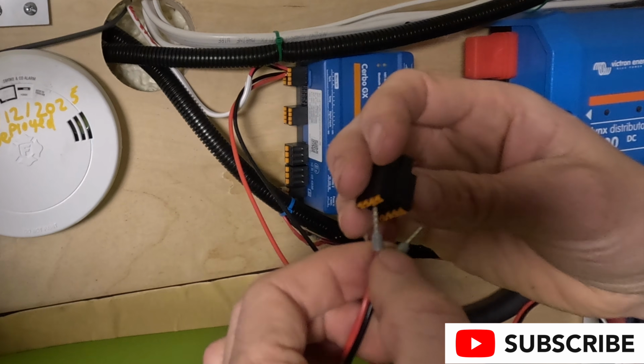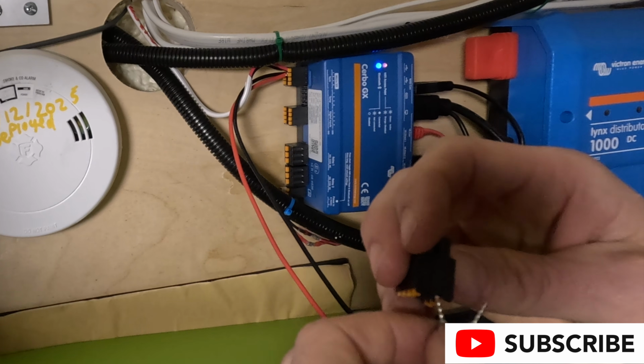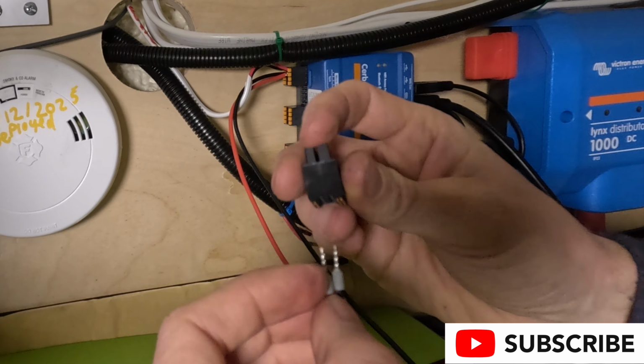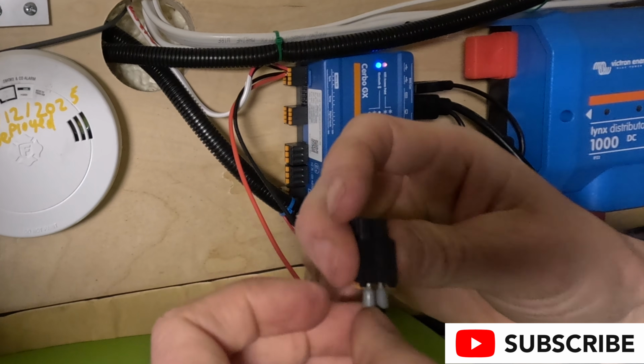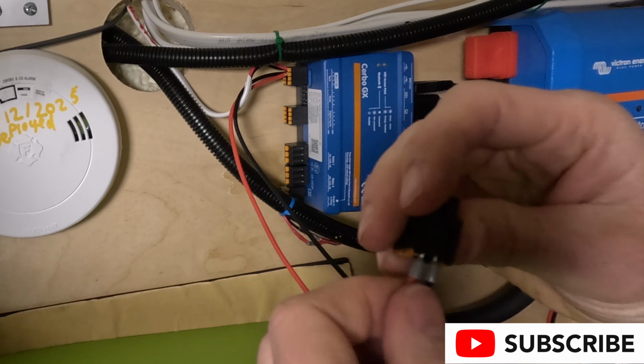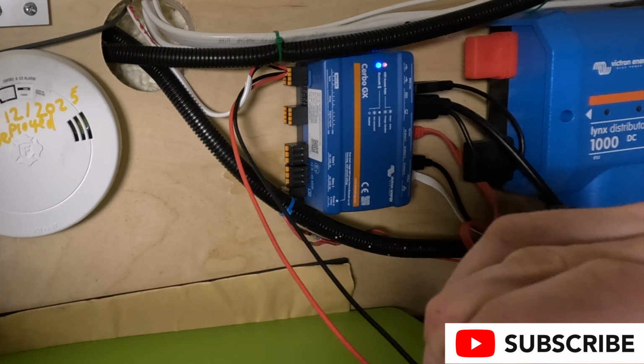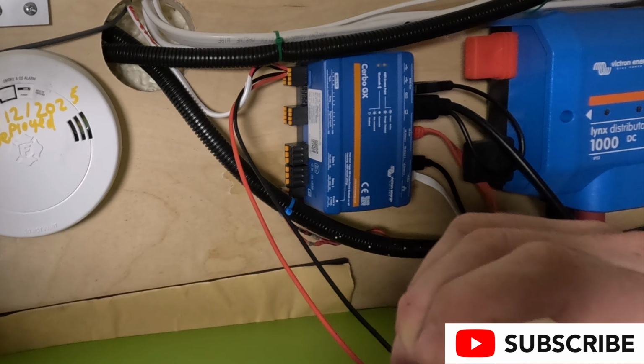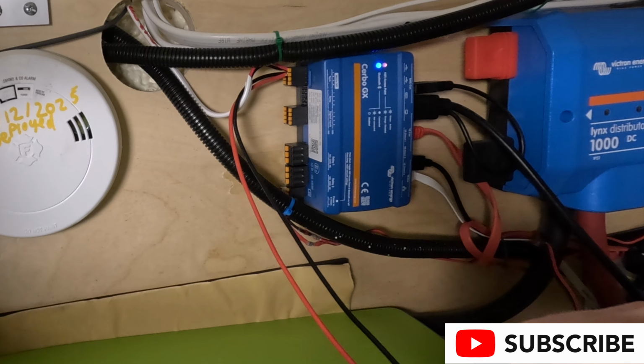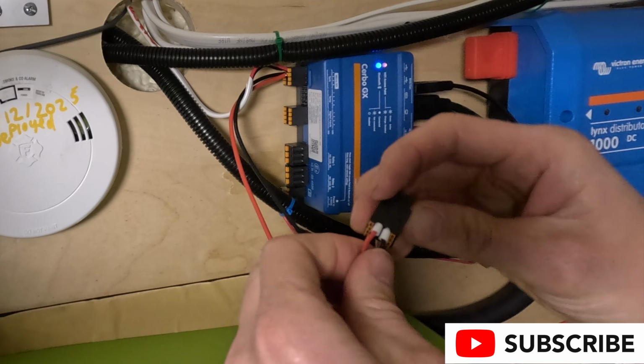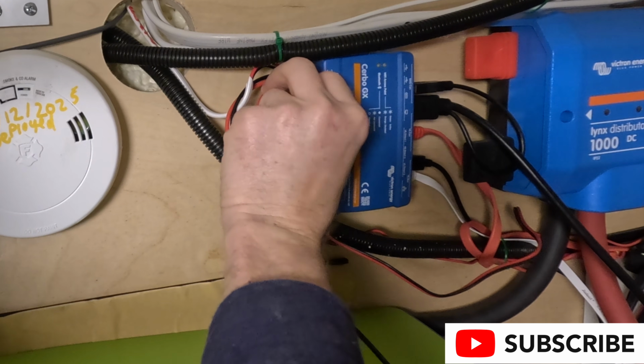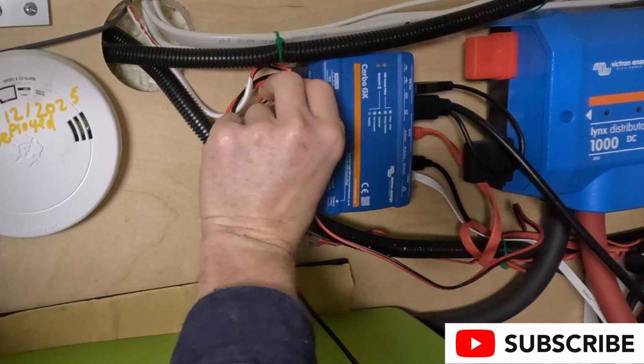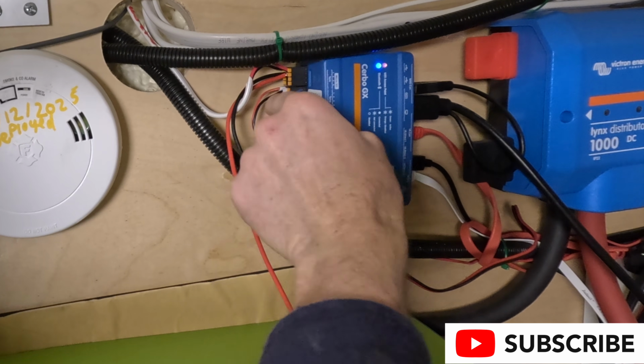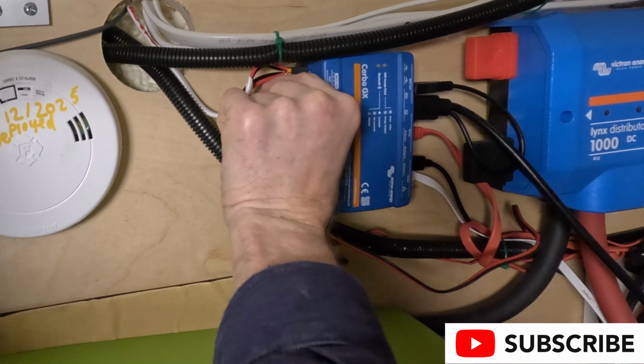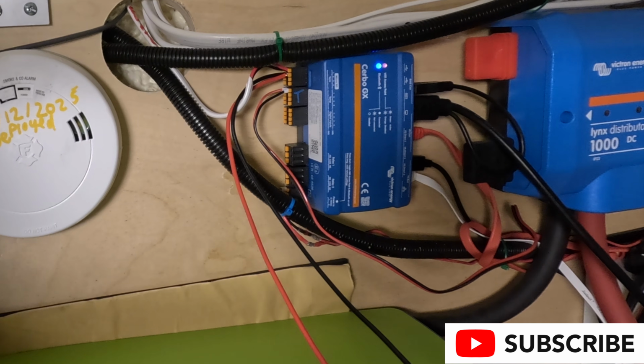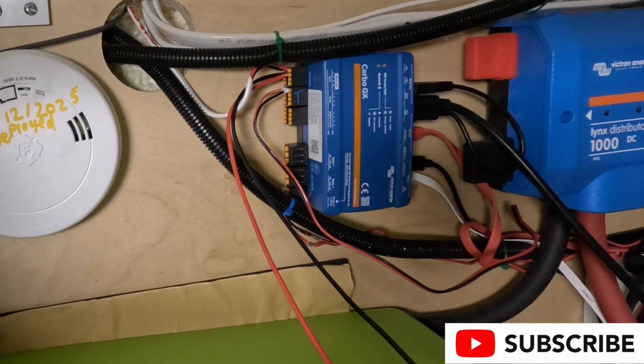Note, if you cut the stock ferrules off the red and black conductors and put your own on, they may not fit as well, even if they're the same size. So it may make sense to go ferrule free and stick your wires in the hole without protection. In this case, we've decided on our ferrules and we're plugging this terminal block in like a Lego chip, and we're good to go to our Cerbo GX to start our temperature probe configuration.